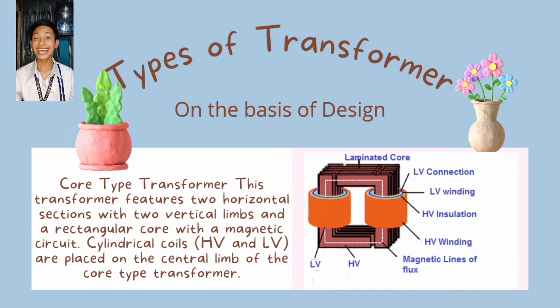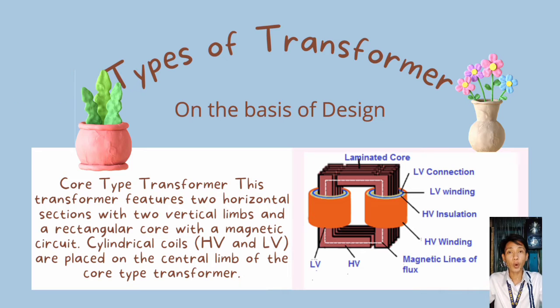Types of transformers and its parameters. First is on the basis of design. First is the core type transformer. This transformer features two horizontal sections with two vertical limbs and a rectangular core with a magnetic circuit. Cylindrical coils, for high voltage and low voltage, are placed on the central limb of the core type transformer. As you can see in the picture below, that is a core type transformer. It has a laminated core, the low voltage connection, the low voltage winding, the high voltage insulation, high voltage winding, and magnetic lines of flux.